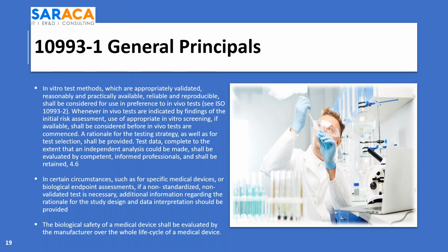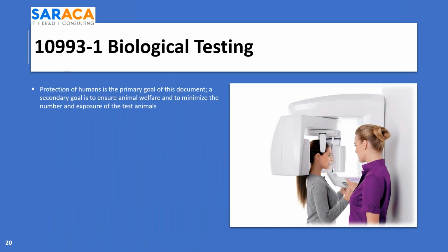The biological safety of a medical device shall be evaluated by the manufacturer over the whole life cycle of a medical device. So is there any certain frequency defined in the standard at which the biocompatibility assessment has to be done after product launch? There is no frequency specified. You, as part of your risk assessment in your design, need to consider at what point would be appropriate to do testing for degradation of your product over time. I don't think it would be appropriate to do time 0 and time 30 years. So you need to pick out something that you can defend and that would make sense from literature search and study the materials in use in a biological system.